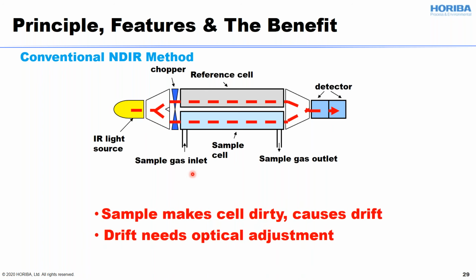But we still have the problem of dirty sample gas being introduced into this sample cell, which will damage the sample cell and cause drift. And drift needs optical adjustment. And another problem is that you need to split the light power 50% by 50%, but in a plant, you will see a lot of vibration there. There's a lot of noise, and that will affect this division.